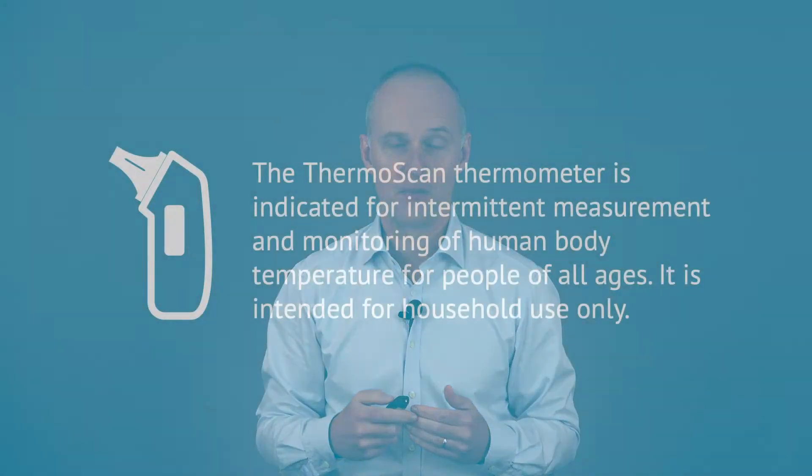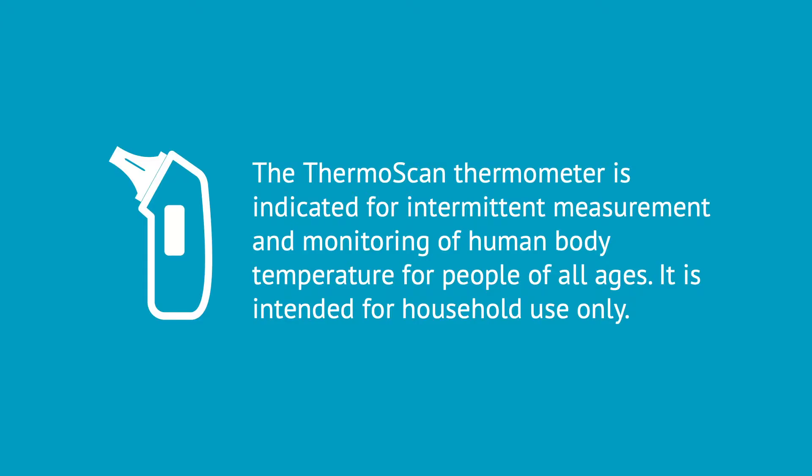The first term I will bring up is intended use. It is a good starting point because the intended use or intended purpose is something you should have defined quite early in your projects. Here is an example for a thermometer: the ThermoScan thermometer is indicated for intermittent measurement and monitoring of human body temperature for people of all ages. It is intended for household use only.